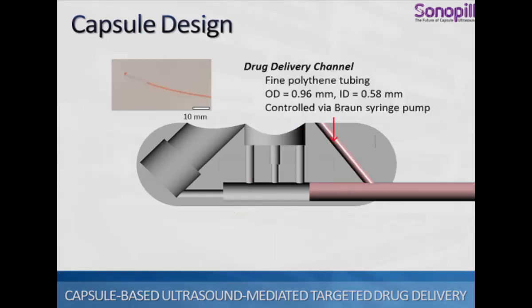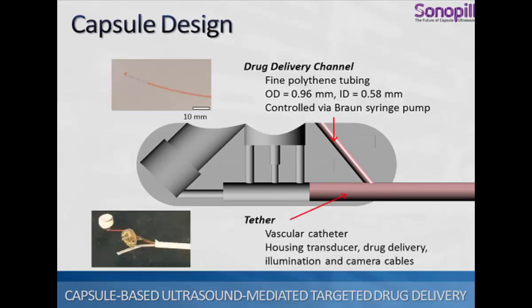So now a bit about the drug delivery channel. The drug delivery channel consists of a fine bore polythene tubing with an outer diameter of around 1 millimeter. It can be seen on the top left image here. It's got red food dye in it just for visibility. And it's controlled out with the capsule also via a syringe pump. And the tether consists of a vascular catheter. It's got an outer diameter of around 2 millimeters. And each of the cables of each of the components is passed through this.